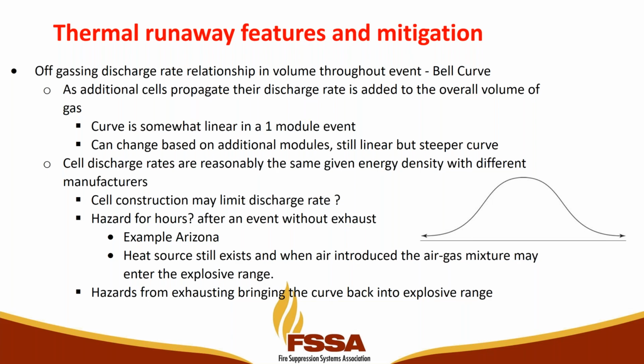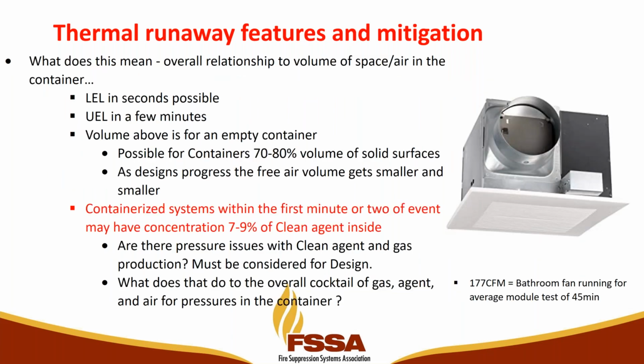The question we have is, what happens if you've exceeded the upper explosive limit? What happens if you vent and bring it back into an explosive range - are you going to initiate an explosion? Is it better to do that while you have trained personnel on site, or wait it out? I'd say prepare for it and have people on site. LEL is possible in seconds, UEL in a few minutes.